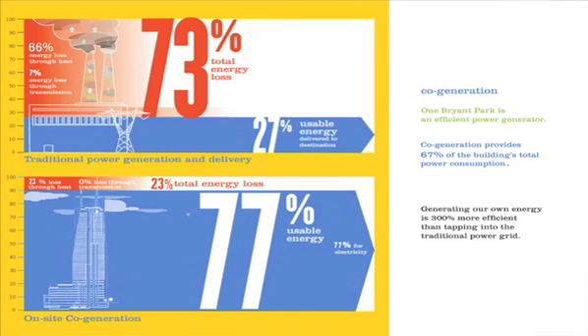What we're doing at Bryant Park is building our own cogeneration plant, our own power generating plant. It'll generate 4.6 megawatts of power, which is about enough for 5,000 homes, and it's generated in an extremely clean way, where we lose very little up the smokestack. There is some loss, about 23%, but we get 77% usable energy, three times more than what you get out of the traditional power distribution system. A much better, efficient, cleaner way of producing power for the building, and it's the first building to really include this on a large scale in a single building. You'll see them on hospitals and in university complexes, but never in a large scale building of this type.